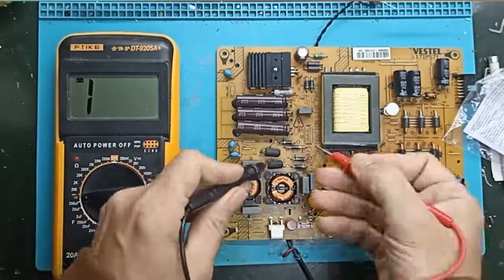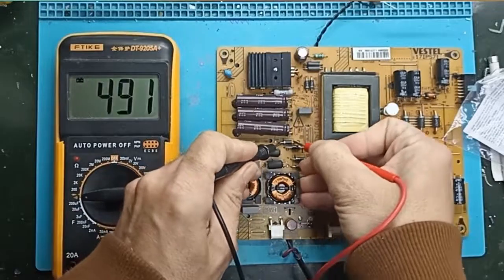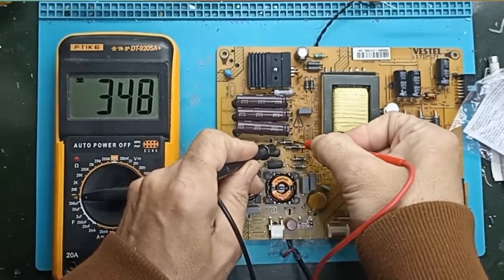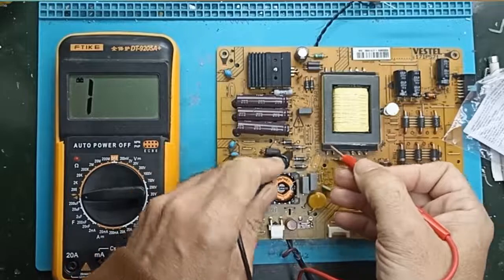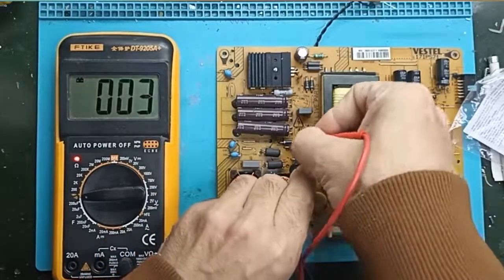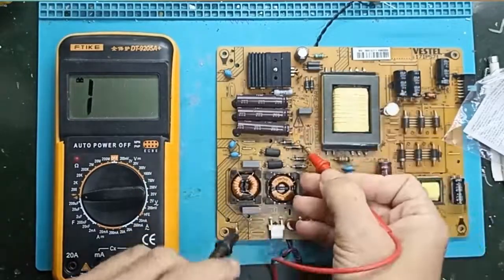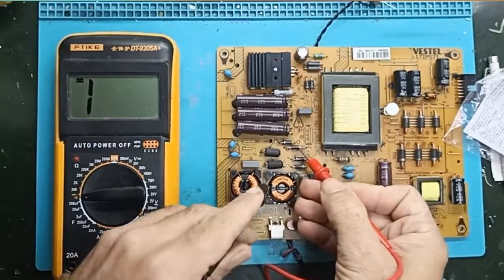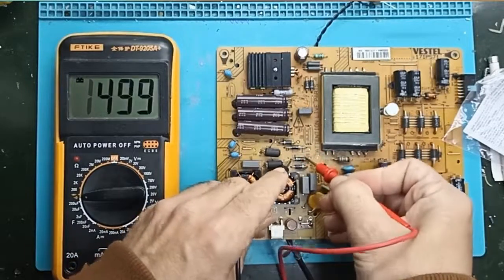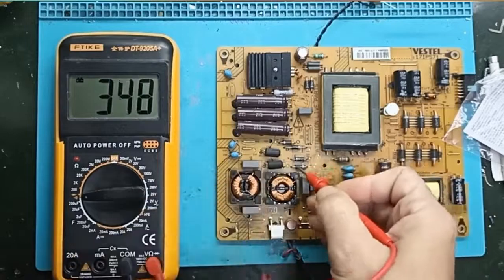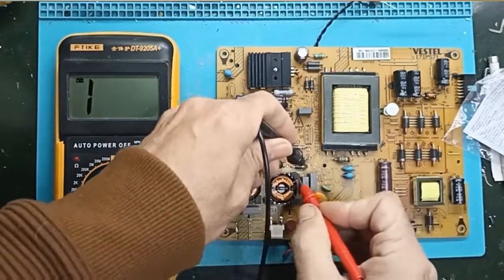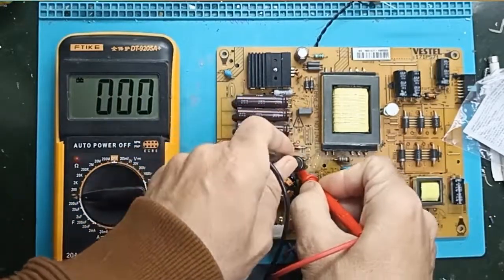So I measure the first diode over here, and it shows me that the first diode is correct. I'll go to the second. Here I find a short circuit. See, this one shorts. Let's continue to the other. This one, good. And last, this also shows a short circuit. Short circuit diodes shown here. Some diodes are shorted.